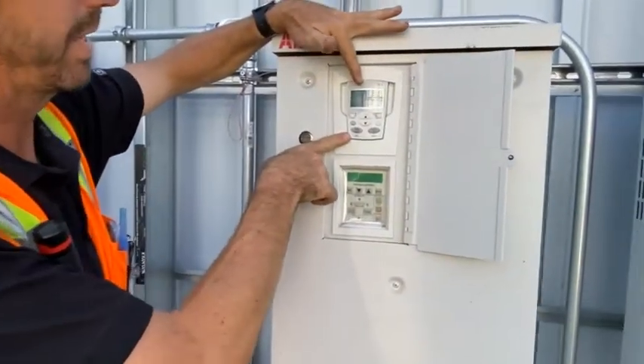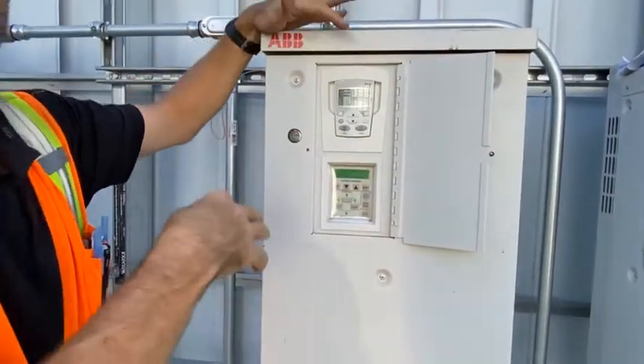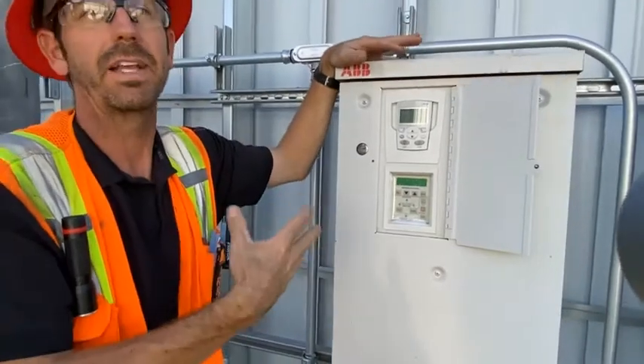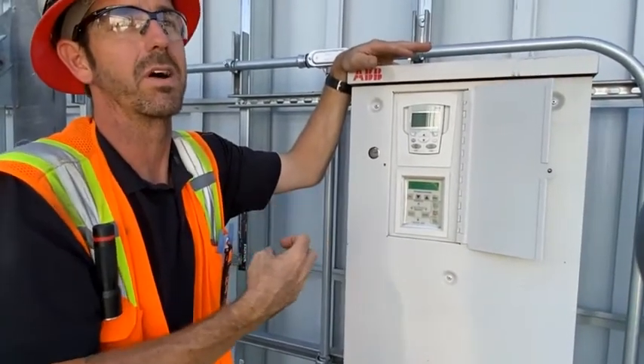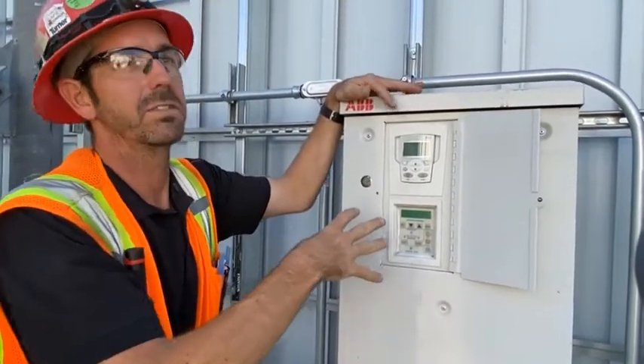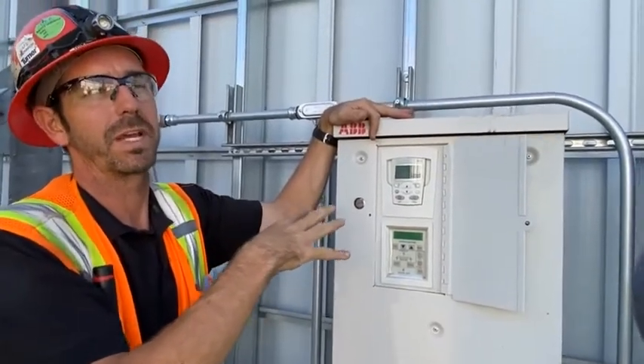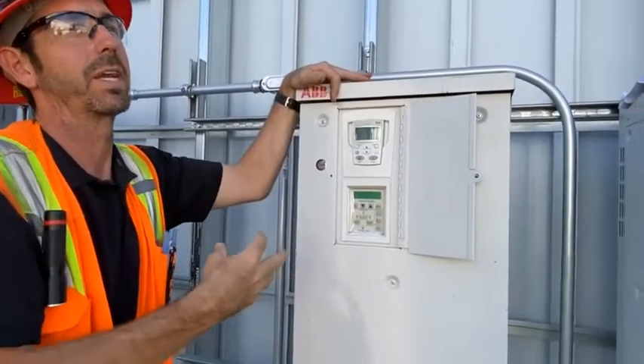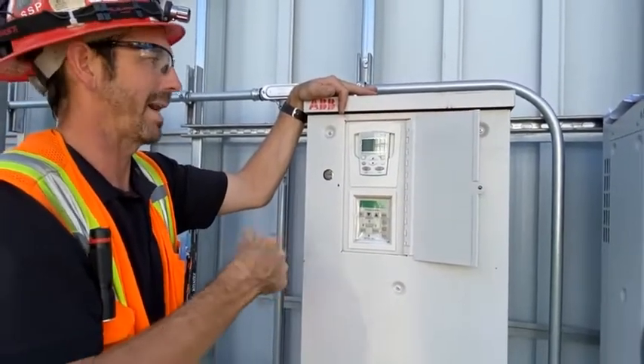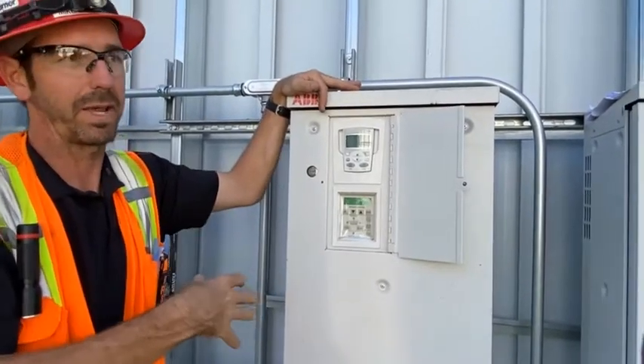The drive is where the capacitors are, see how it's still running. These drives aren't really big, so the capacitors aren't that big. They don't store their power as long. But just know the VFDs do store power in the capacitors. We want to make sure when we do isolate power, we give the drive a long enough time for the capacitors to dissipate their charge, okay?